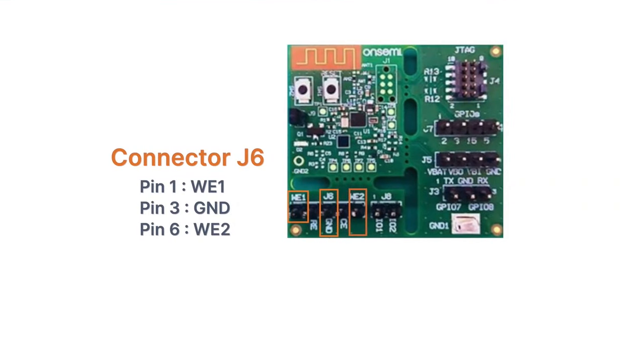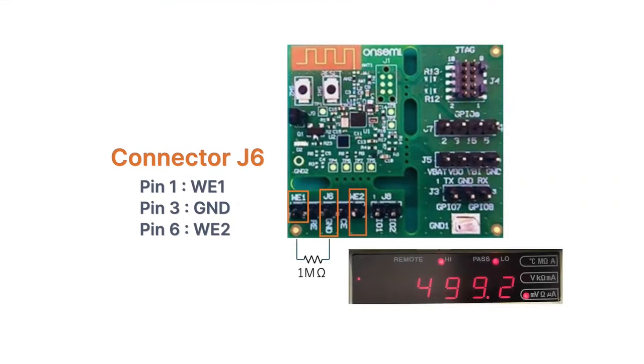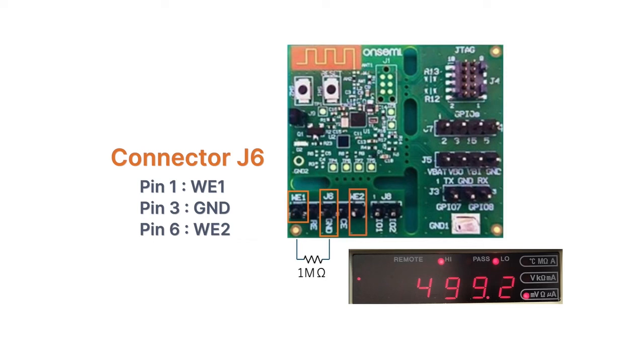You can examine the accuracy of current measurement at WE1 by inserting a resistor between WE1 and ground. In this case, the resistor is set to 1 megaohm between WE1 and ground. The CEM-102 BASIC sets the WE1 voltage to approximately 499.2 millivolts. You can confirm calibration is complete by checking that the WE1 voltage value, typically around 500 millivolts by default, has stabilized.